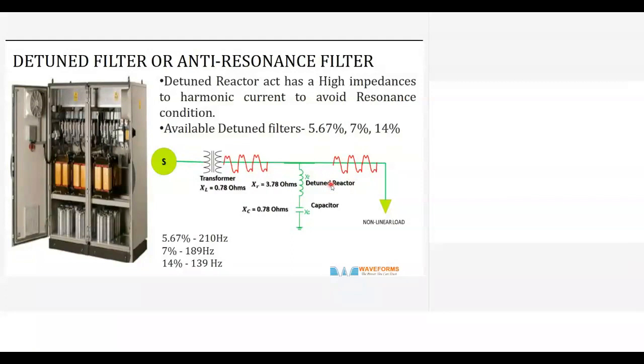Okay, yeah. So if I want to block the seventh harmonic, what percentage should I choose? Should I go for 14% or 7%? Normally they use 7%, but you can use 5.6. Normally everybody uses 7 because it is in between the 5th and the 7th. I don't know, somehow they use the 7% one. My doubt is, the seventh harmonic is 7 times 50 hertz. So 7 times 50 hertz is around what? 350 hertz. Yes, 350 hertz.